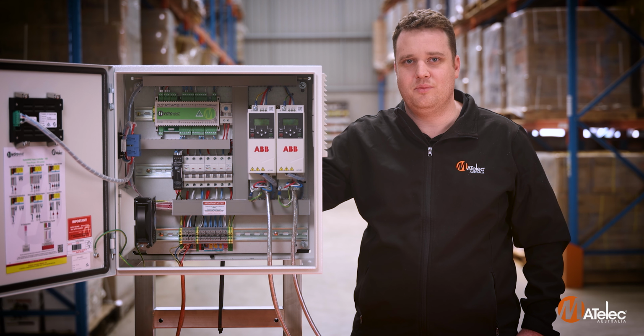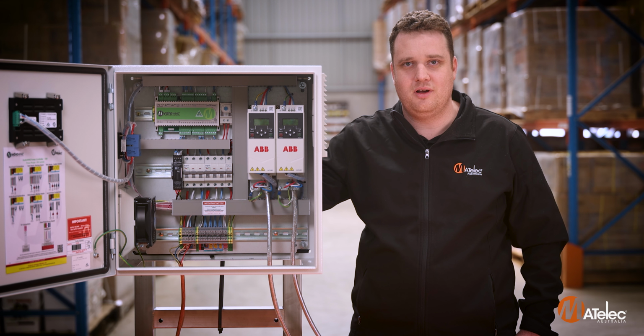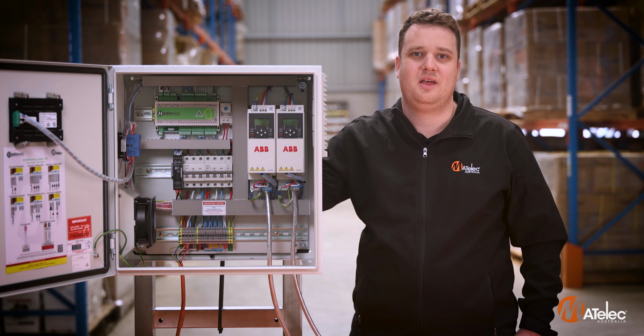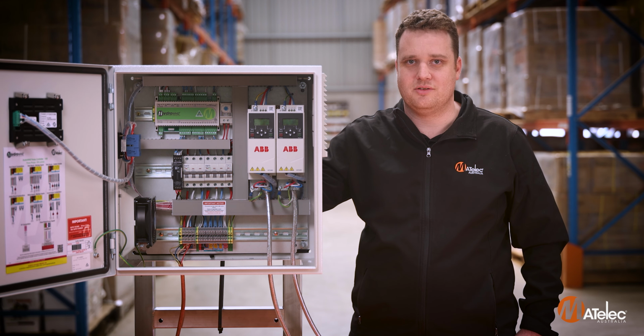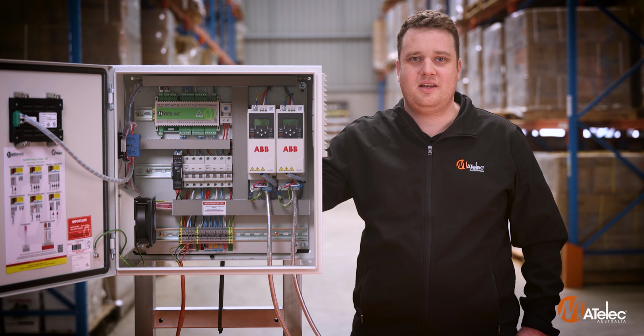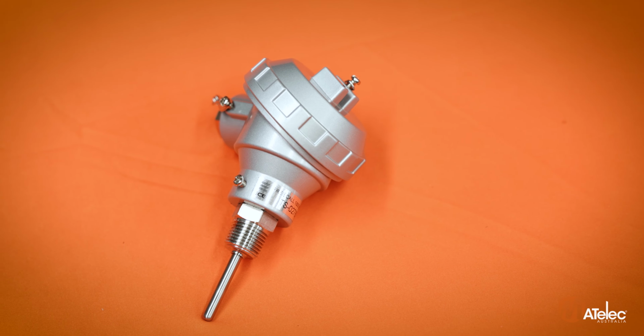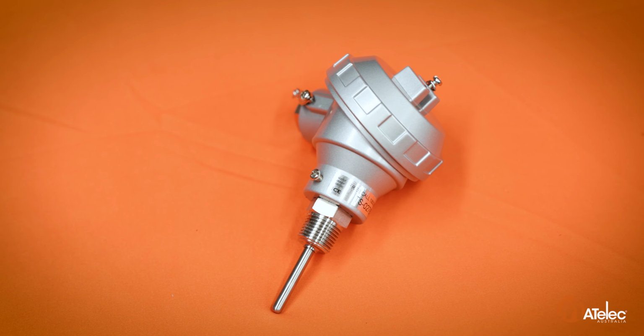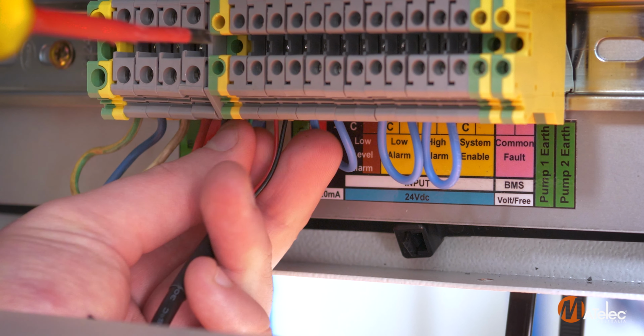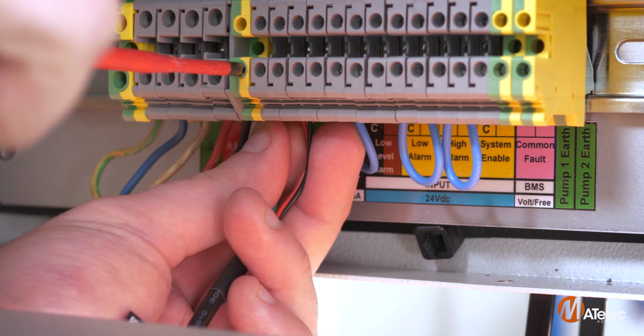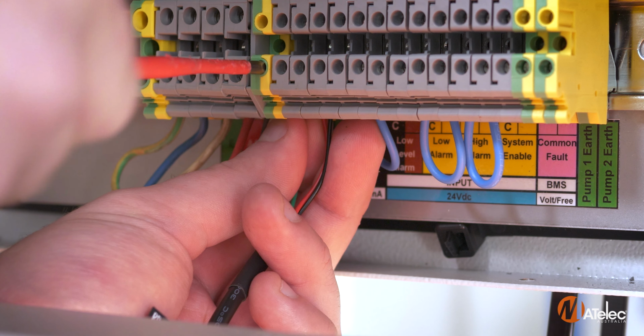For this example, we're using a standard dual pump controller with variable speed drives. Here's how the temperature connections work. In a standard temperature connection, a temperature transducer 4 to 20 milliamp is your primary control. Connect it to the analog input terminals and make sure the shielding is also connected to the earth terminal.